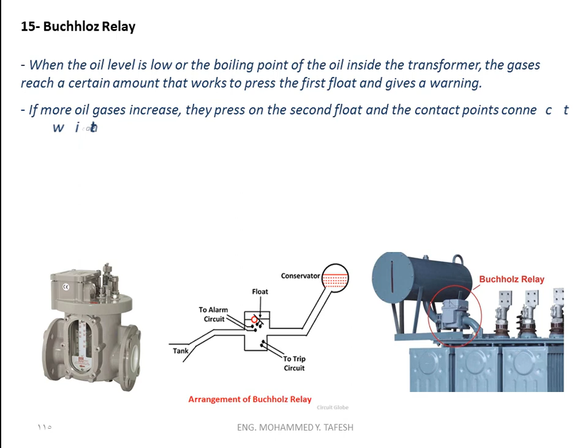When the oil level is low, or the oil inside the transformer boils, the gases reach a certain amount that presses the first float and gives a warning. If the gases increase further, they press the second float, and the contact points connect, directly triggering the disconnection of the circuit breaker.